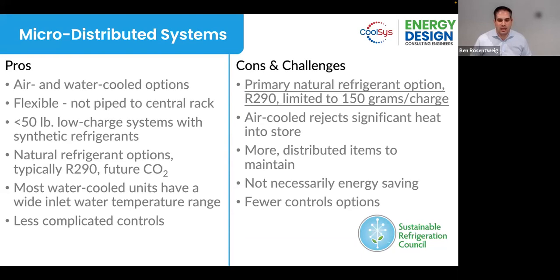And based on the construction codes and other regulations, there is a limit of 150 grams per charge with these systems. Therefore, you need many, many compressor systems throughout the store in order to comply with that. When that charge limit is increased, the flexibility will be enhanced and there'll be more options, less compressor systems, etc. If you go with air-cooled equipment, it does reject significant heat into the store, which can be used, but also can cause a significant load on your HVAC system. And if you implement something like this without looking at that, you could have a problem.